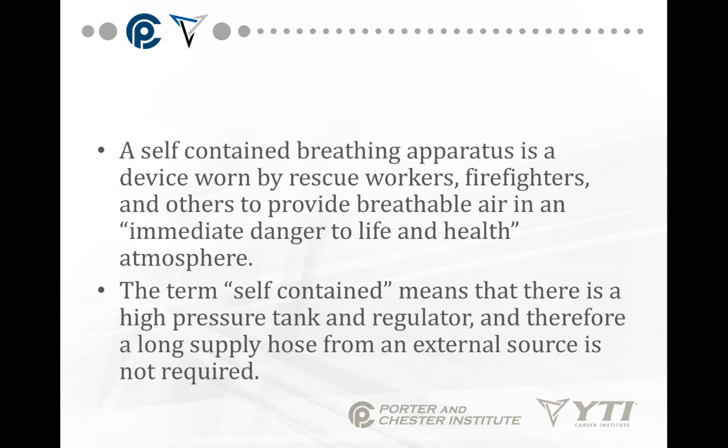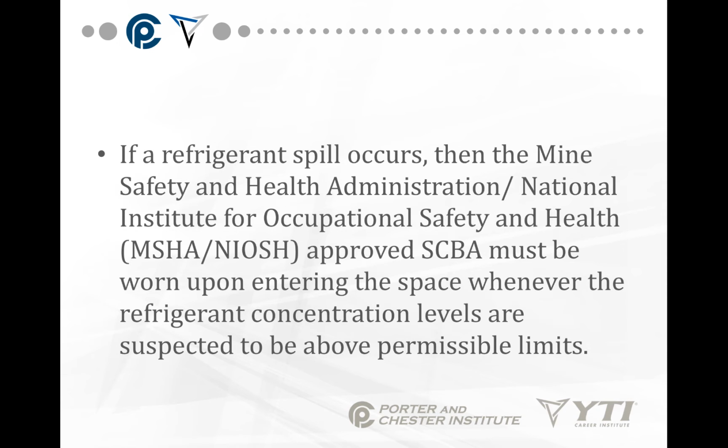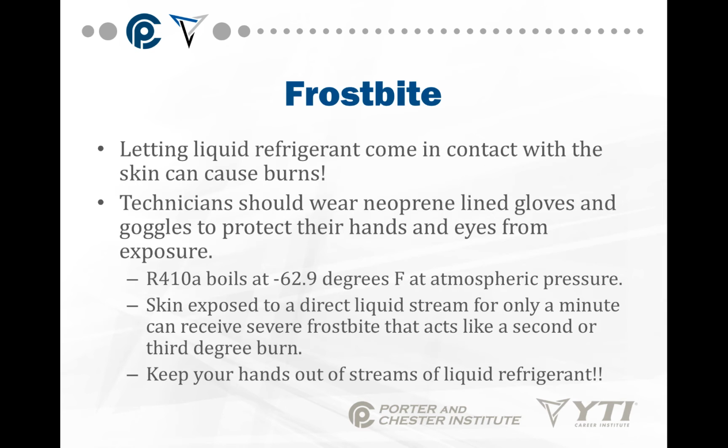A self-contained breathing apparatus is a device worn by rescue workers, firefighters, and others to provide breathable air in an immediately dangerous to life and health atmosphere. The term self-contained means that there's a high-pressure tank and regulator, and therefore a long supply hose from an external source is not required. If a refrigerant spill occurs, then an approved self-contained breathing apparatus must be worn whenever entering the space if the refrigerant contents are above the permissible limits.